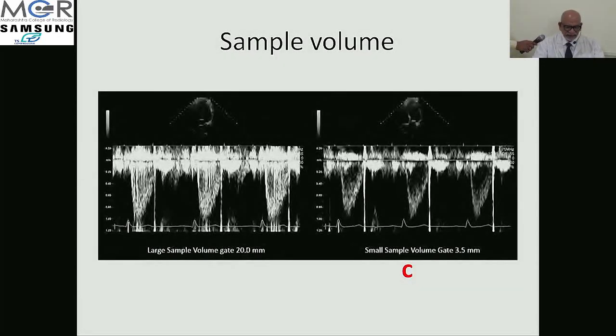So sample volume, just an example where the bigger sample volume is used, you can see that the whole envelope is filled, and this looks as if a lot of frequencies are there. But if you reduce the sample volume to a particular area only, a small sample volume, you can see only small frequencies of sound or Doppler.